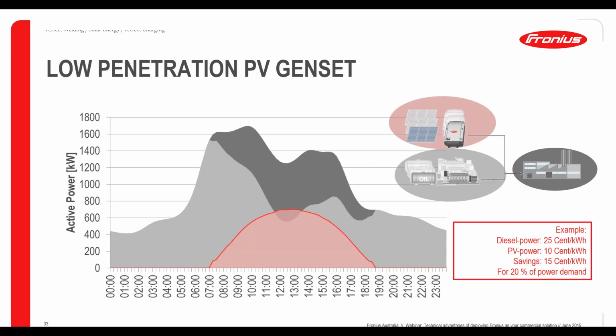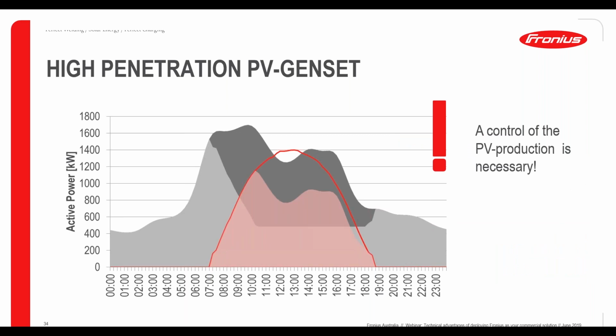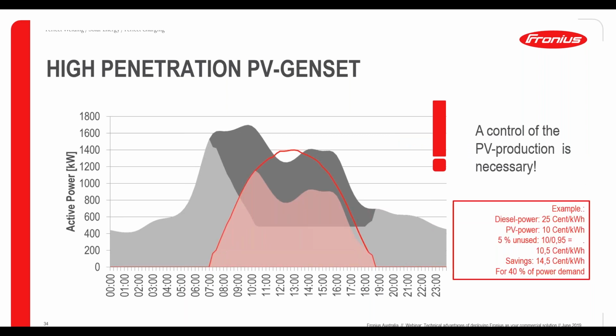There's a low penetration scenario, whereby the solar is only taking up, let's say, 20 to 30% of the total peak load. You'd also have a high penetration genset, whereby the solar is a larger percentage of the peak load. So we'd need to be able to control and, for example, ramp the inverters up and down so that we keep within the guidelines of the PV genset setup. You can see on the right-hand side that there are particular savings as to how it all comes together. But let's have a look at all of the componentry firstly.